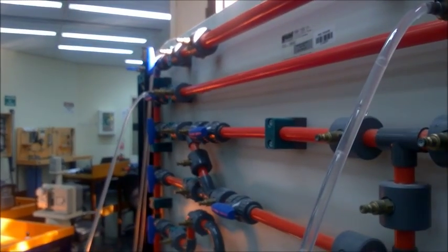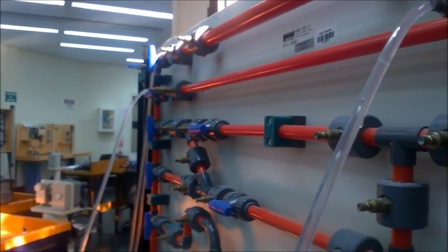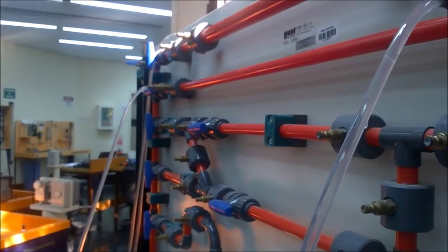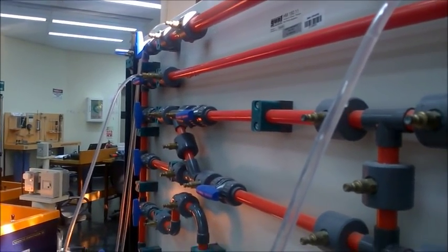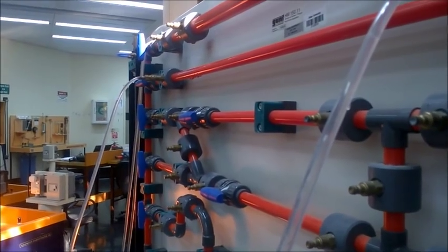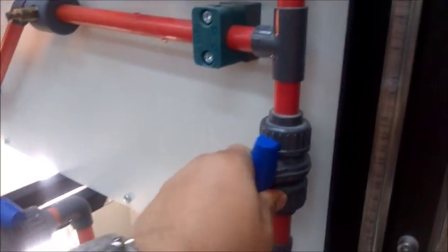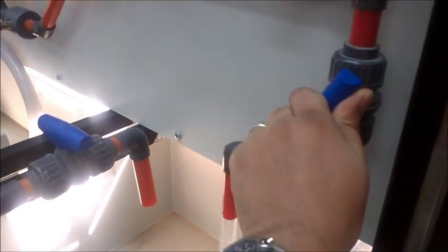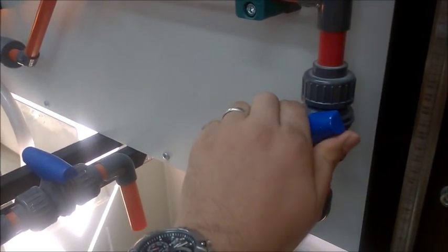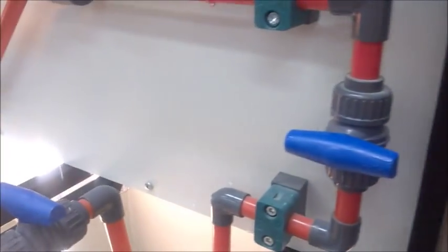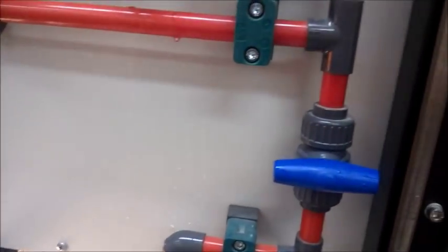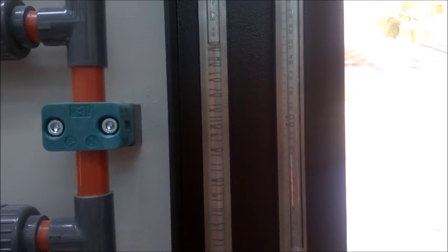As we did before, we want to get rid of all air bubbles from the system. Now you can see the air bubbles from the pipe and the hoses. Close and open the flow control valve several times until all air bubbles are removed. Then close the valve.